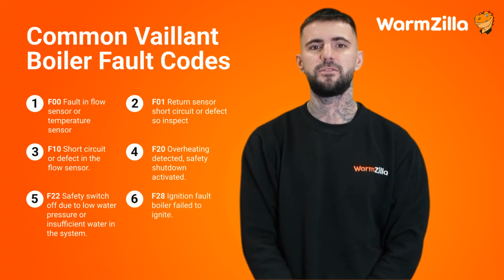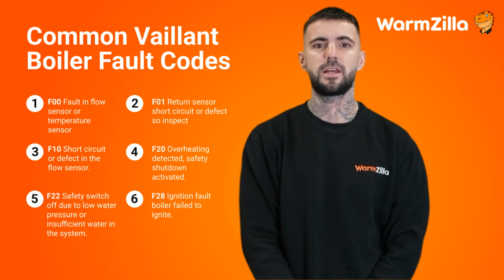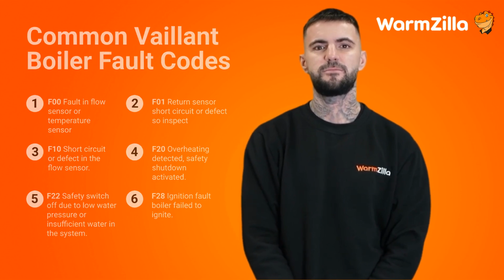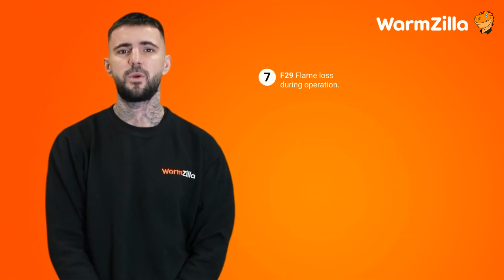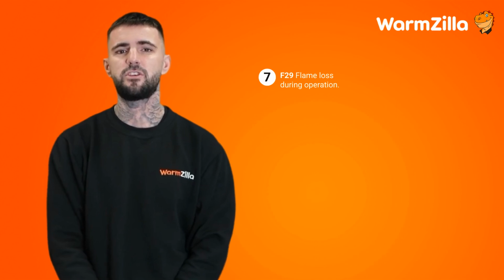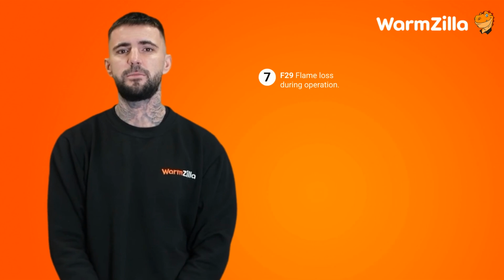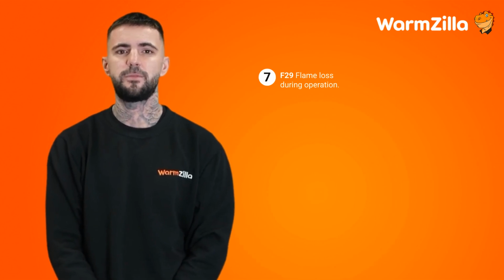F28 is the ignition fault, meaning that the boiler failed to ignite. Just check the gas supply, ignition electrodes, and ensure the condensate pipe isn't blocked. Error code F29 means there's a flame loss during operation. You'll need to inspect the gas pressure, check for drafts or blockages, and reset the boiler.